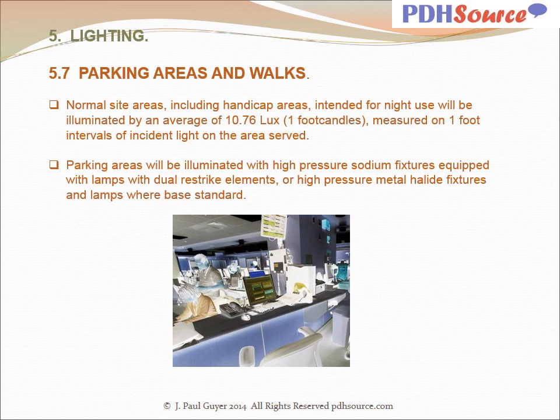Normal site areas, including handicap areas intended for night use, will be illuminated by an average of 1-foot candles measured on 1-foot intervals of incident light on the area served. Parking areas will be illuminated with high-pressure sodium fixtures equipped with lamps with dual restrike elements, or high-pressure metal halide fixtures and lamps where base standard.